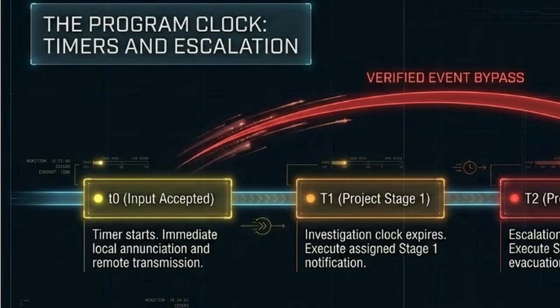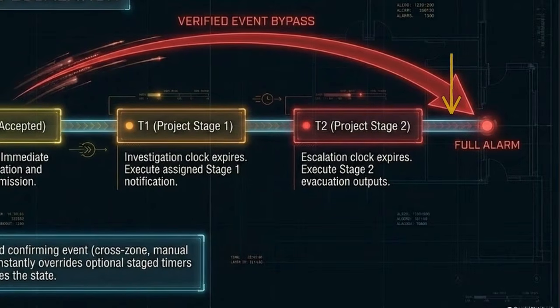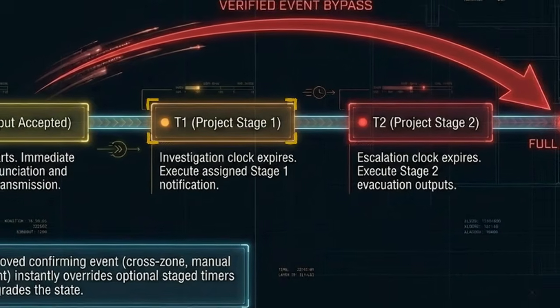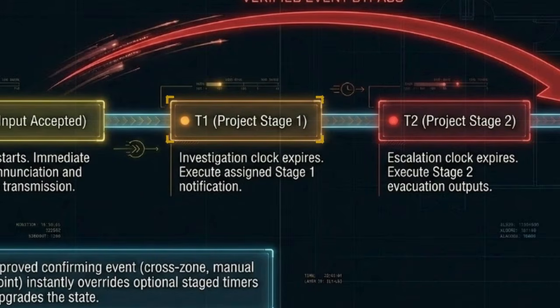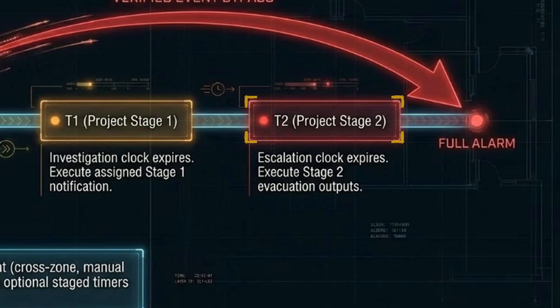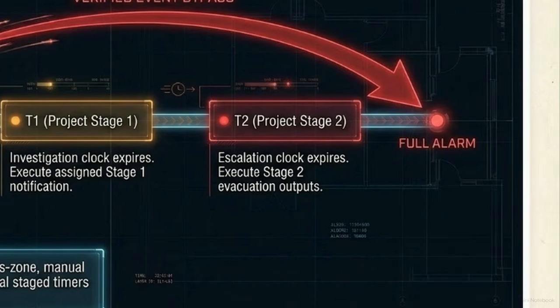This timeline outlines the program clock. Once the panel accepts an initial input at T0, it does not instantly dump suppression. It starts a strictly governed escalation of time. For a staged alarm, an investigation clock begins. If the technical staff cannot resolve the issue before T1 expires, the matrix executes Stage 1 notifications. If the escalation clock reaches T2, the system automatically triggers Stage 2 evacuation outputs.